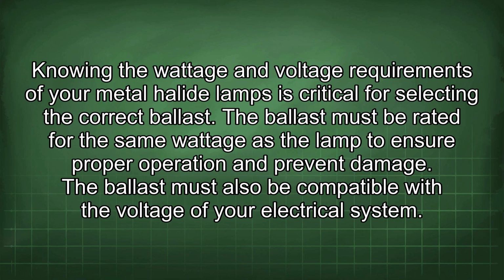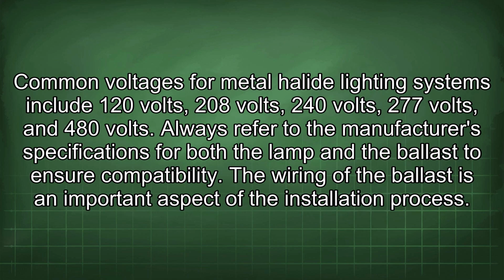Knowing the wattage and voltage requirements of your metal halide lamps is critical for selecting the correct ballast. The ballast must be rated for the same wattage as the lamp to ensure proper operation and prevent damage. The ballast must also be compatible with the voltage of your electrical system. Common voltages for metal halide lighting systems include 120 volts, 208 volts, 240 volts, 277 volts, and 480 volts. Always refer to the manufacturer's specifications for both the lamp and the ballast to ensure compatibility.